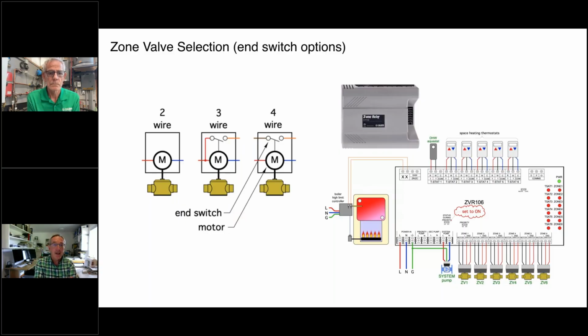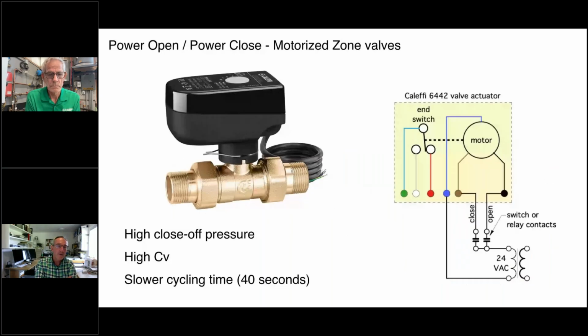Another option that Caleffi has is what I call a power open, power close motorized zone valve. This is a ball valve rather than a paddle, but it doesn't have a spring in it. So you have to power it open, and I believe it takes about 40 seconds to open. And you also have to power it closed. And the circuitry is shown over here. Basically, these are switch or relay contacts. When you want the valve to open, you put 24 volts between the blue wire and the black wire, and that will motor the valve open.